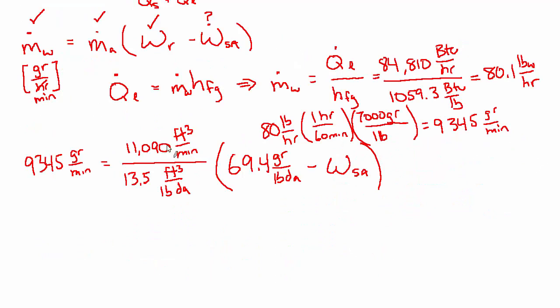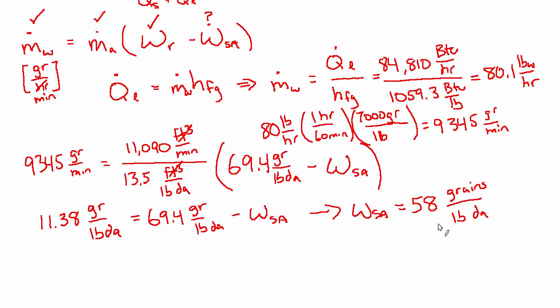And now we have an algebra problem. So we can divide this, we'll get rid of cubic feet, this will become pounds per minute, and then we divide the 9,345 by that. We end up with 11.38 and that now has units of grains per pound of dry air, equals 69.4 grains per pound of dry air minus the humidity ratio of the supply air. And then we can rearrange and solve for the humidity of the supply air: 58 grains per pound of dry air. And just in case you were preferring to work on this problem in pounds of water instead of grains, it's simply multiplying or dividing by 7000. But for your reference it's 0.0083 pounds of water per pound of dry air, and that is answer B.